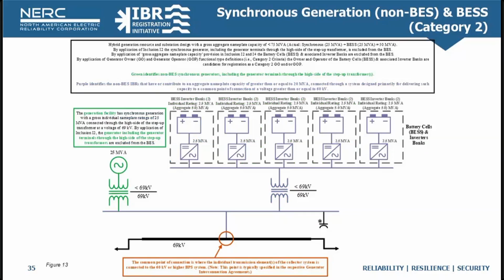This is our final example of synchronous generation together with an inverter-based resource. And this hybrid generation resource and substation design consists of a synchronous generation and battery energy storage with an aggregate nameplate capacity of less than 75 MVA. The hybrid generation resource consists of one synchronous generator rated at 25 MVA and 10 inverters individually rated at 2.5 MVA, making up the battery energy storage component for an aggregate nameplate capacity of 50 MVA. Again, the common point of connection in the orange circle is at a voltage of 69 kV.